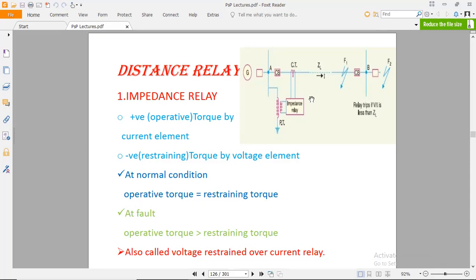So this is the internal structure of the impedance relay, which is also called the distance relay. It is implemented in our power transmission line, fixed at this end, and it senses potential by the PT, the potential transformer, and current from the power transmission line as well. CTs sense the current and PTs sense the potential, which are provided to the impedance relay. The user defined impedance is provided in the relay, the set point we take from this side, and the comparison is based on the normal and abnormal condition.